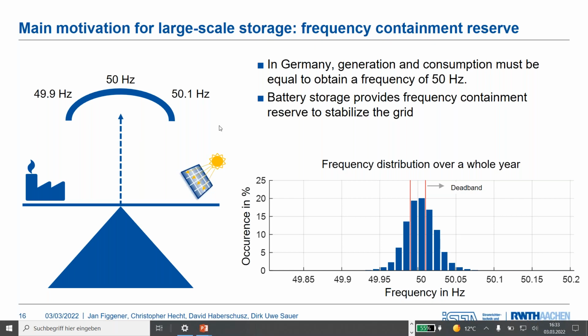On the right-hand side, you see a frequency distribution over a whole year. Here you see the occurrence in percent on the y-axis over the frequency in hertz on the x-axis. And you can see that the deviation of frequency is quite small. So for most of the values, we're in the range of 49.95 hertz to 50.05 hertz. So that is a very small deviation. And most of these deviations are also in the dead band.